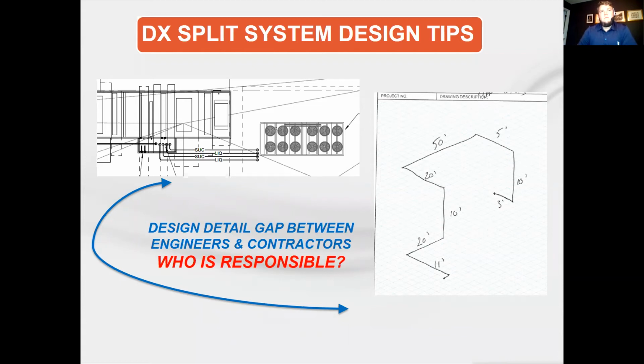We feel it'd be helpful to have some guidance as to what those sizes are for the manufacturer that you base the design on. The little drawing on the right here was something the contractor sent to us. We asked for a piping drawing, and that's what they sent to us. The condensing unit was down here where the 11-foot leg is, and the air handler was up where the 3-foot leg is, if I remember right. And the guy went ahead and started piping, and it was contentious. We had to make some changes, and it just seems like we ought to take more care.